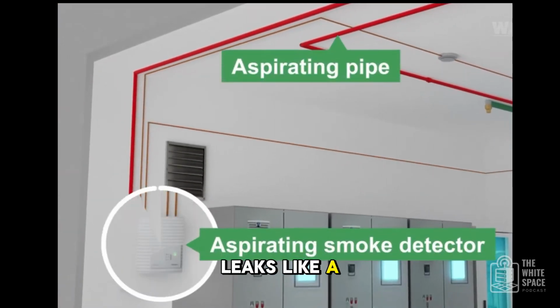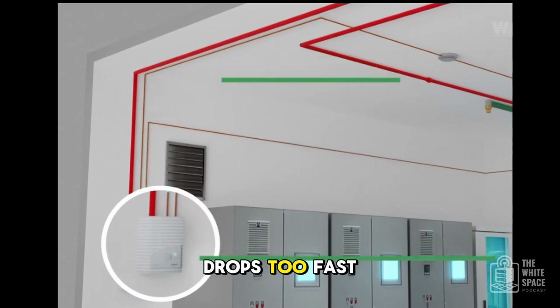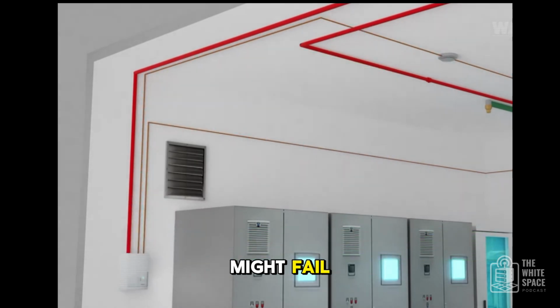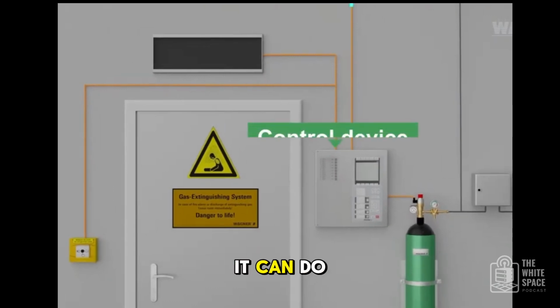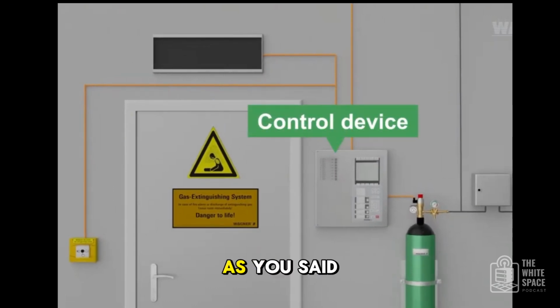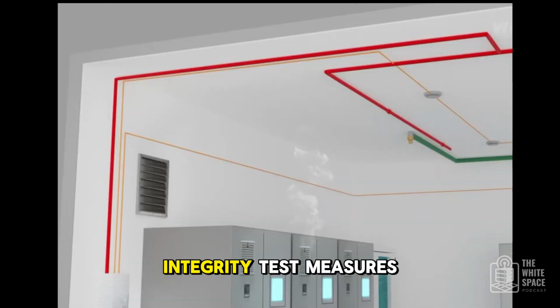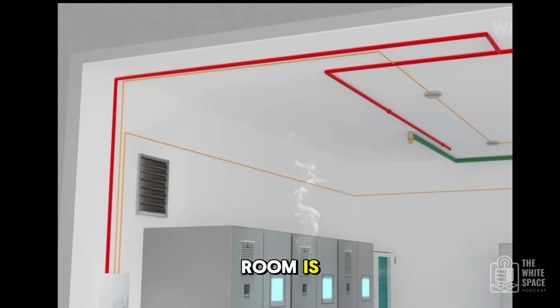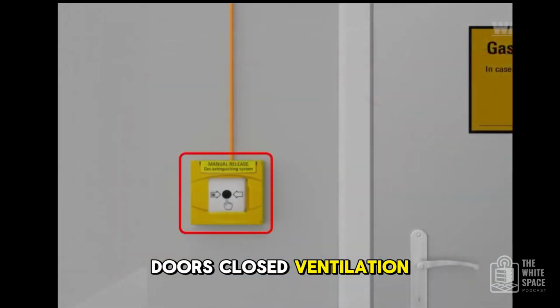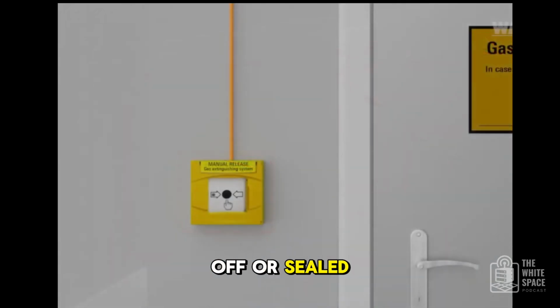If the room leaks like a sieve, the gas concentration drops too fast, and the suppression might fail. Right. The gas just escapes before it can do its job, like filling a leaky bucket, as you said. Exactly. So the room integrity test measures how leaky the room is. How do they actually do that? Well, first, they seal up the room as tightly as possible. Doors closed, ventilation systems temporarily dampered off or sealed.